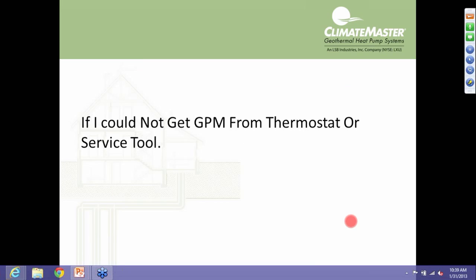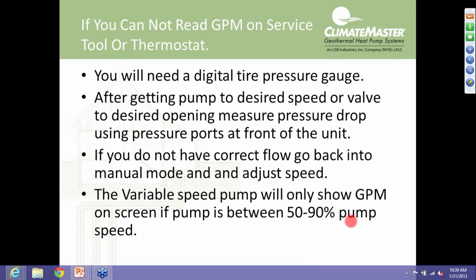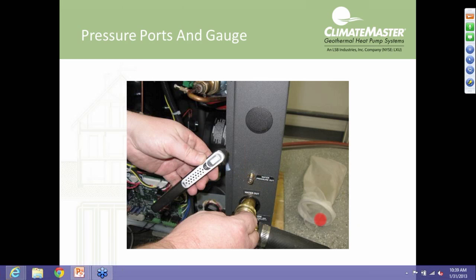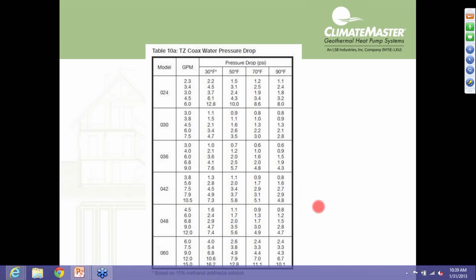Now, if we cannot see GPM on that thermostat or the service tool, we've got to get out that digital tire pressure gauge. We're going to run that pump speed up or down, or that valve position up or down, until we get the pressure drop on these pressure ports. You see right here, pressure ports on the front of the heat pump, using our digital tire pressure gauge. Not the PT ports that are typically here at the water connections. If we use those, those are not the pressure drop across the coaxial heat exchanger. We must use the pressure ports. And that's an automotive Schrader port, just like what's on your car tire. Again, in the installation manual, there's a pressure drop chart based on entering water temperature and each model, showing what the flow rate is in correspondence to that pressure drop.